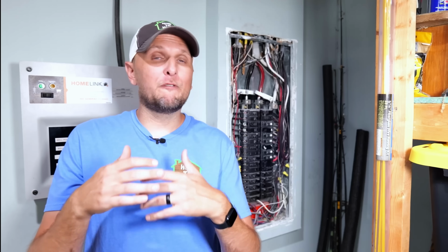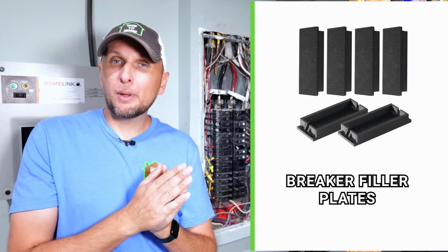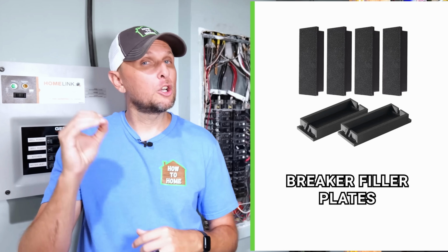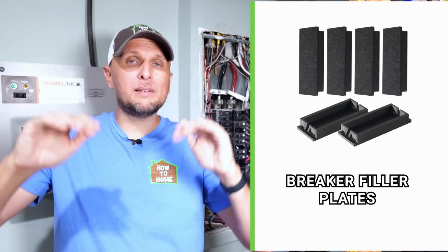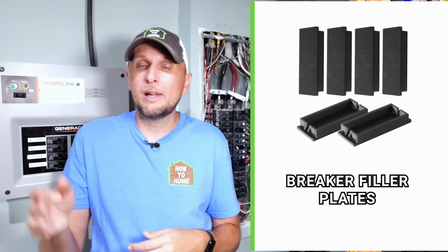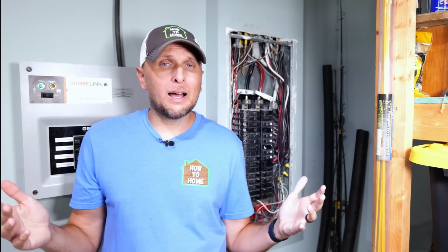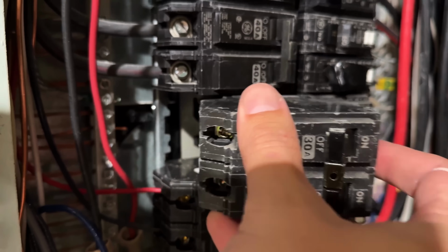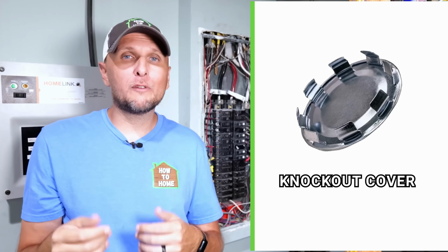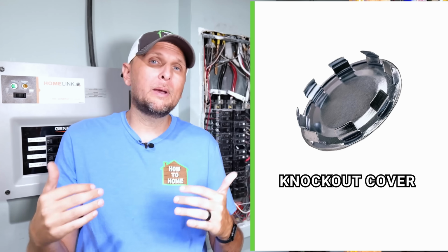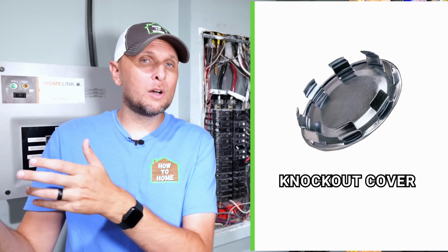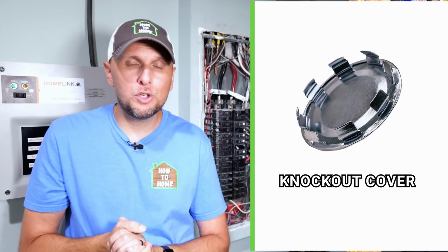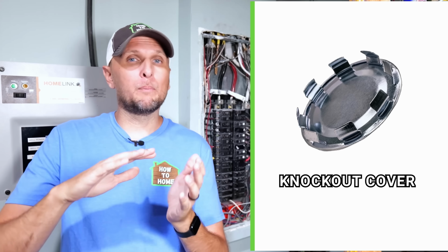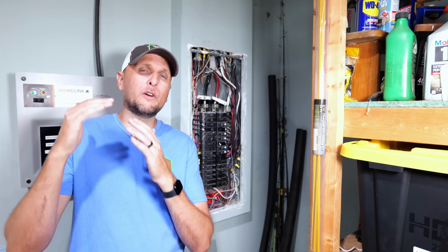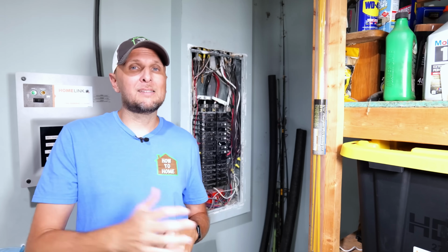The fix is very easy. You can buy filler plates that go into the slots where a circuit breaker used to be, basically flat pieces that cover the slot so nothing can get in. Or you can just leave a circuit breaker in that slot. There are also knockout covers for open knockouts. There's no reason to leave a knockout hole open, since it invites the same problems as a fully open circuit breaker slot. Make sure you cover all open knockouts and slots in your panel.